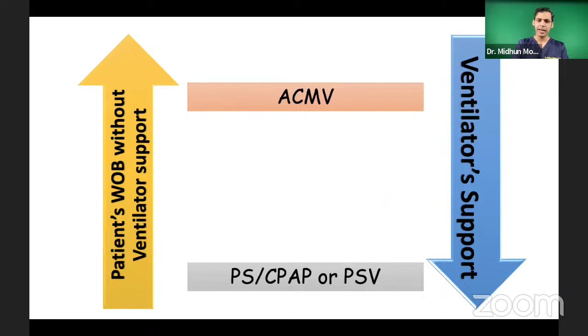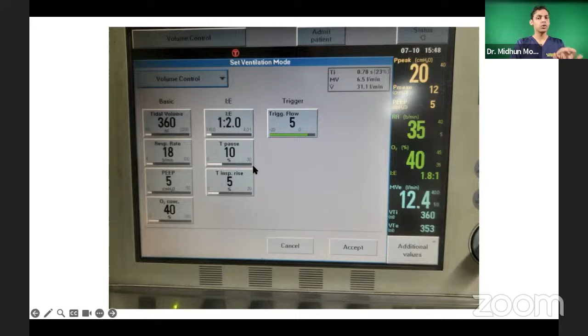So let's see something about ACMV as well as pressure support ventilation here. In ACMV, if you choose that mode, you are going to find these kinds of settings which you need to set. These are the basic settings which you need when you're putting the patient on a ventilator. Usually during intubation, we will sedate and paralyze the patient, and you need the ventilator to provide complete ventilatory support to the patient. So that's when you choose the ACMV mode. Almost all the work of breathing will be done by the machine when you choose the ACMV mode.